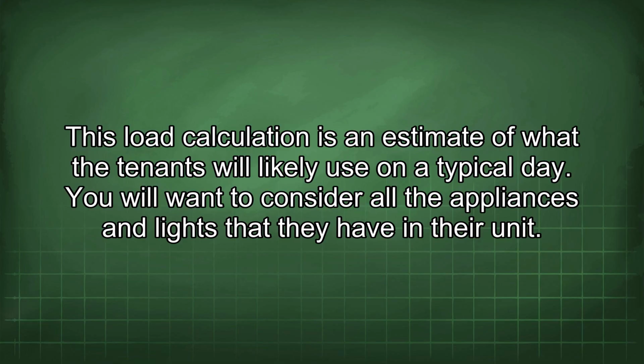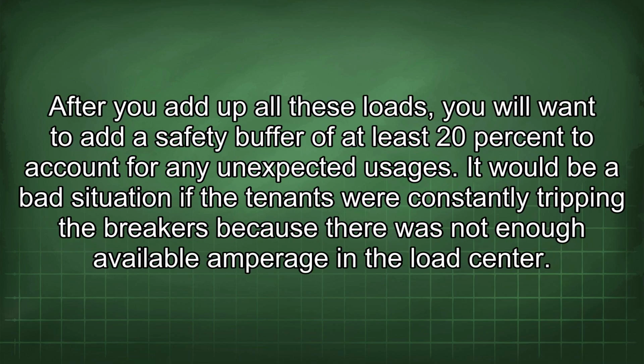You will want to consider all the appliances and lights that they have in their unit. After you add up all these loads, you will want to add a safety buffer of at least 20% to account for any unexpected usages. It would be a bad situation if the tenants were constantly tripping the breakers because there was not enough available amperage in the load center.